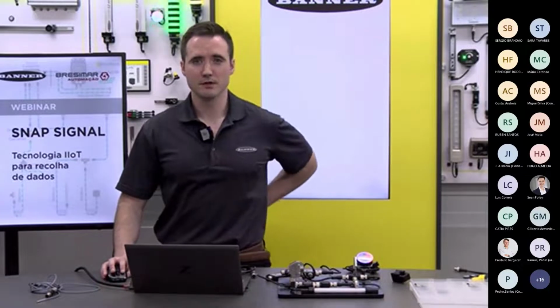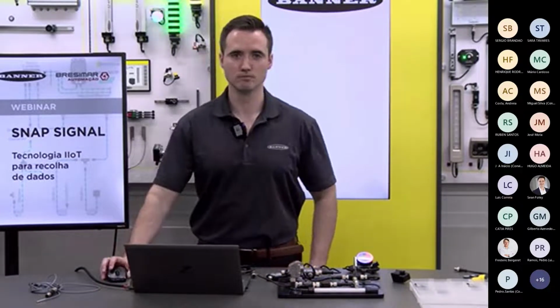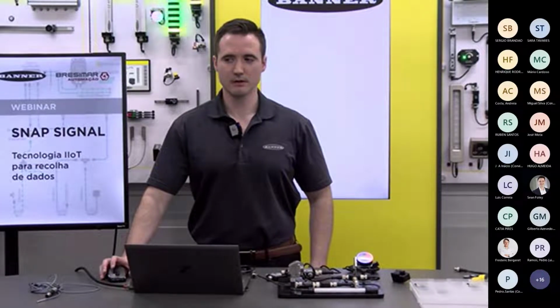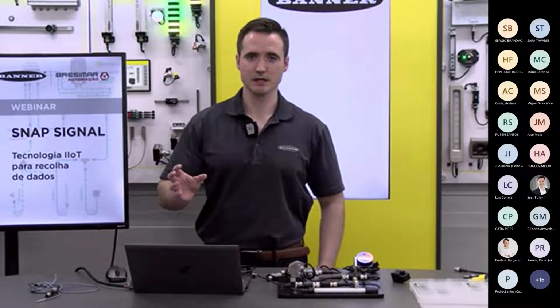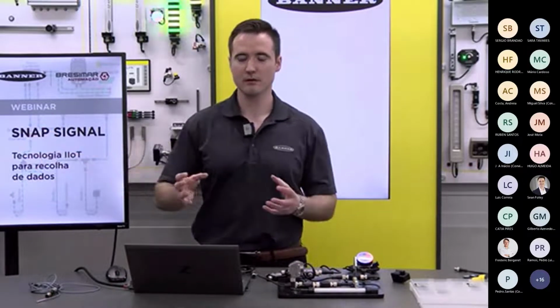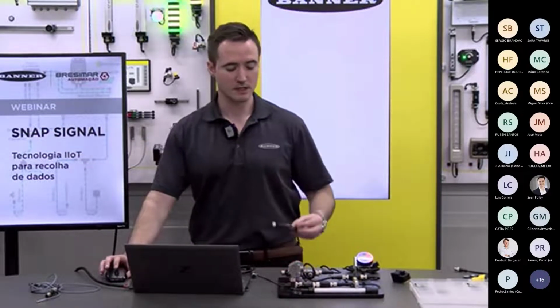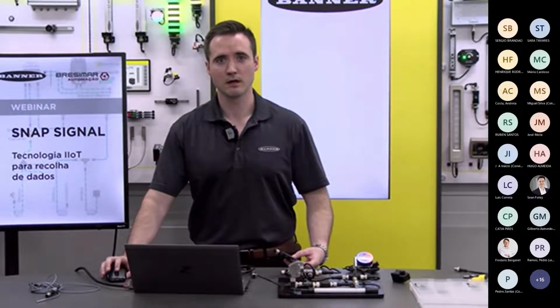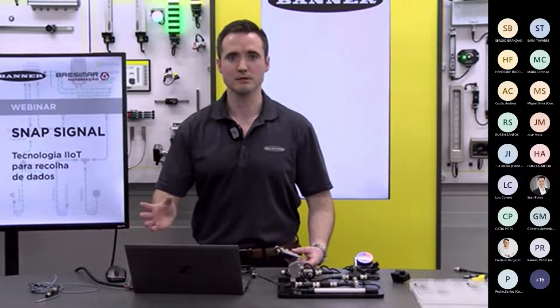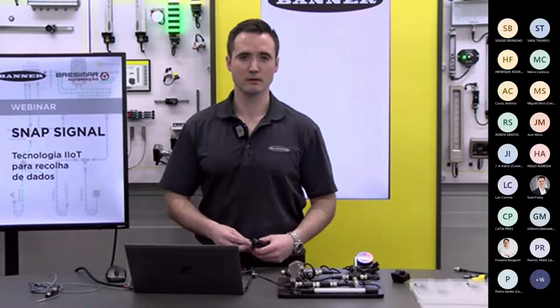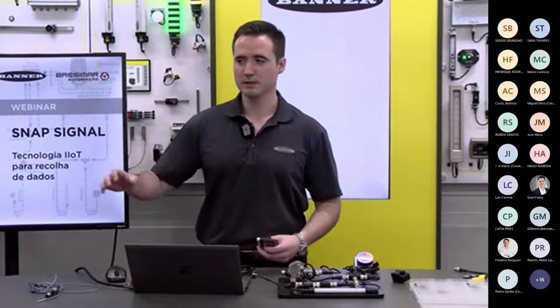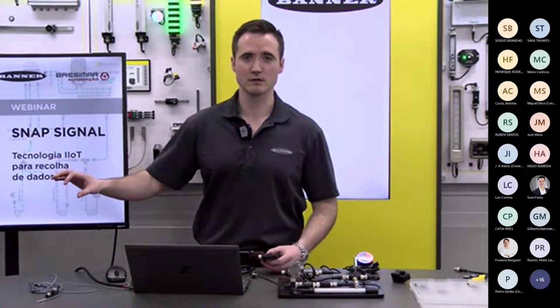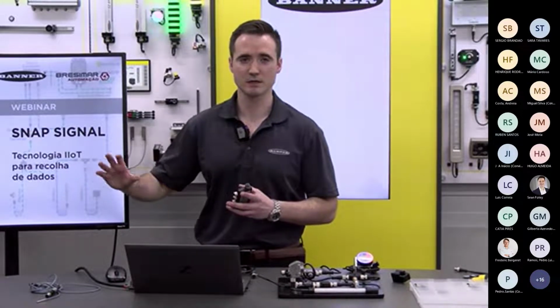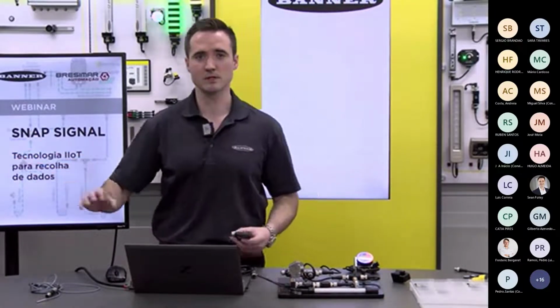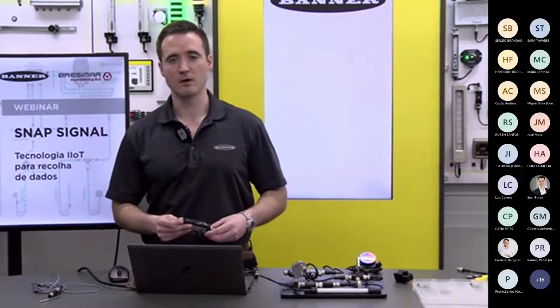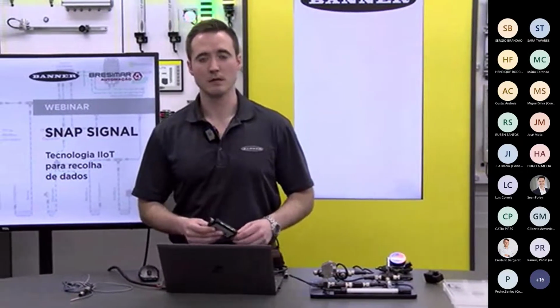So with IO-Link, if they're using an existing IO-Link system, in terms of the overlay, you'd be able to communicate with these IO-Link devices. But our IO-Link masters currently are serial, Modbus RTU. So it depends on what IO-Link devices they're using, but the ability to take IO-Link masters from other manufacturers, we could do as part of the overlay. We're typically not diving into their existing control system, and a lot of IO-Link applications already installed might already be communicating with the PLC.